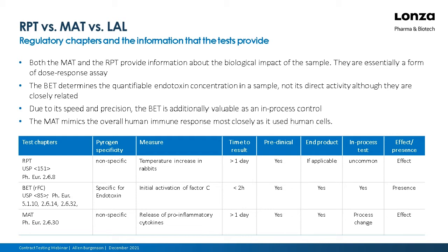And for the monocyte activation test under 2.6.30, again, it's nonspecific. It's looking for the release of pro-inflammatory cytokines. It takes greater than 1 day, and it's, again, actually a 2-day assay. You'll use it for preclinicals, and you could use it for end product testing, and you'd also use it after you've done the comparability and validation, and where you switch over to LAL or RFC, if you have a process change that you think may generate a non-endotoxin pyrogen, such as any cytokine. And you're looking here at an effect.